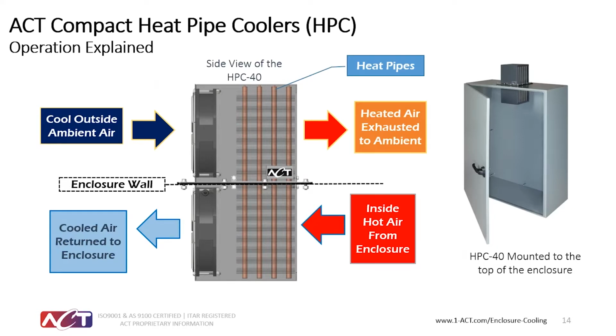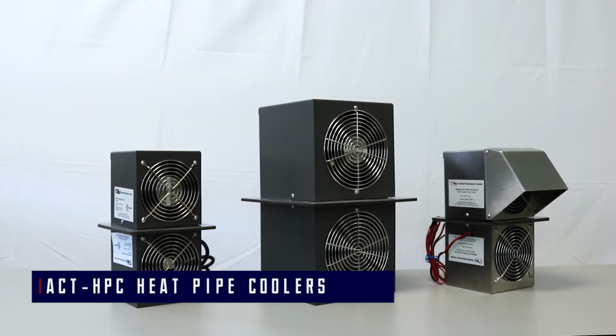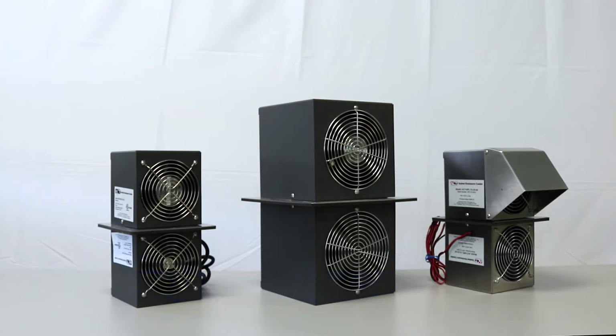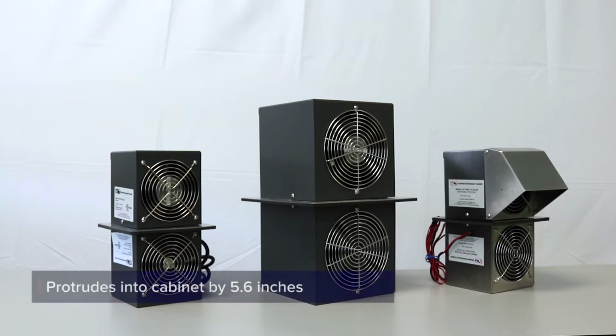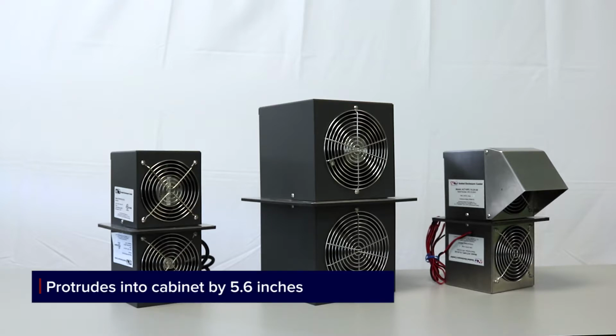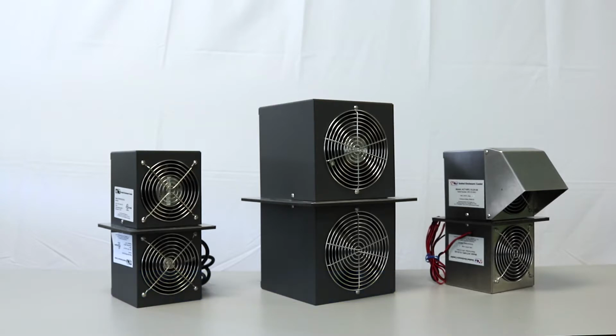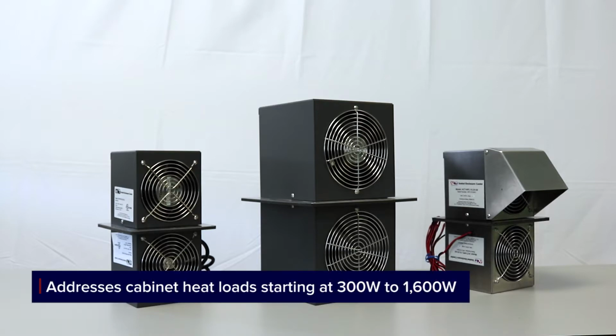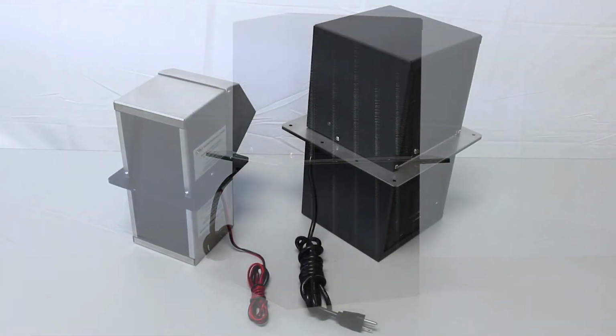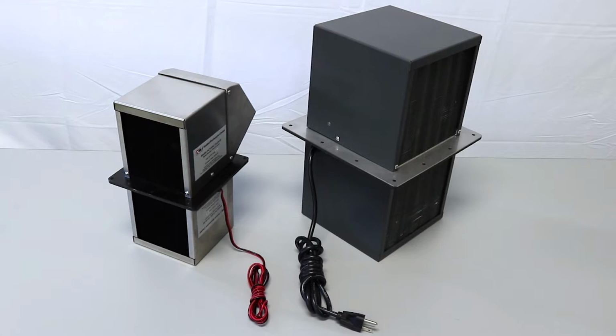The ACT HPC does require more depth on the inside of the cabinet, starting at 5.6 inches of protrusion. A good installation rule of thumb is that there should be about 6 inches of clearance all around the heat exchanger. Special care should be made not to block the airflow with internal enclosure components. The ACT HPC sealed heat exchangers are capable of addressing cabinet heat loads starting at 300 watts to 1600 watts. Applications with higher heat loads can be handled by installing 2 or more enclosure coolers if room permits.